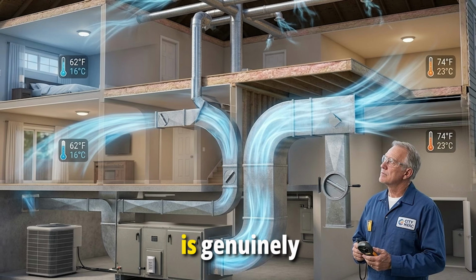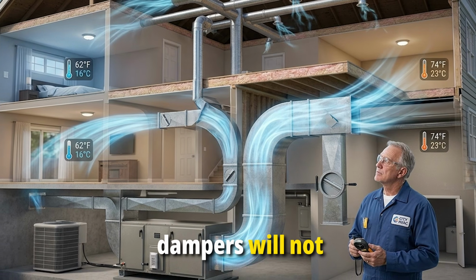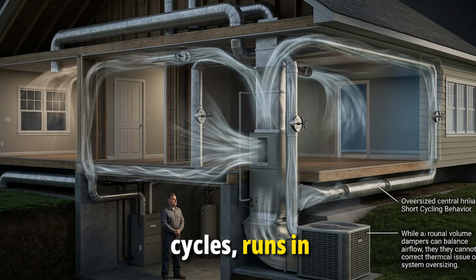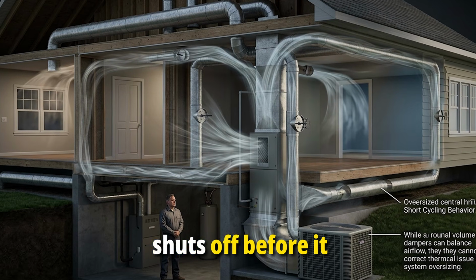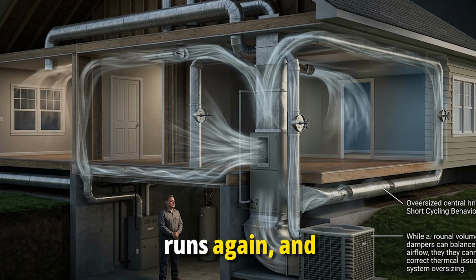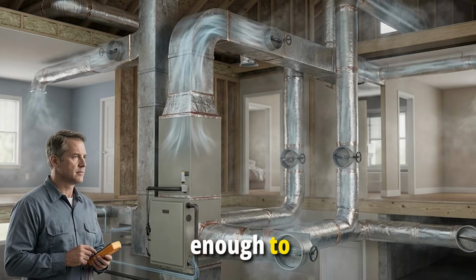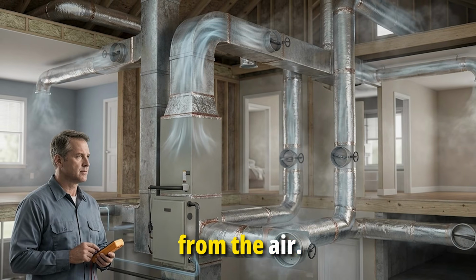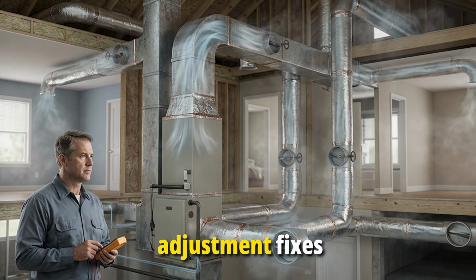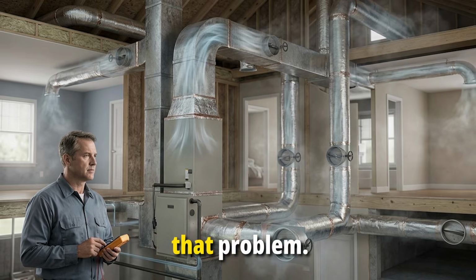If your equipment is genuinely oversized for your home, dampers will not solve that either. An oversized unit short cycles, runs in short bursts, shuts off before it finishes the job, runs again, and never runs long enough to properly remove humidity from the air. No damper adjustment fixes that. It is the wrong tool for that problem.